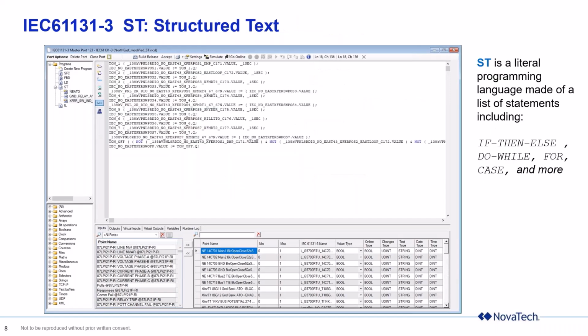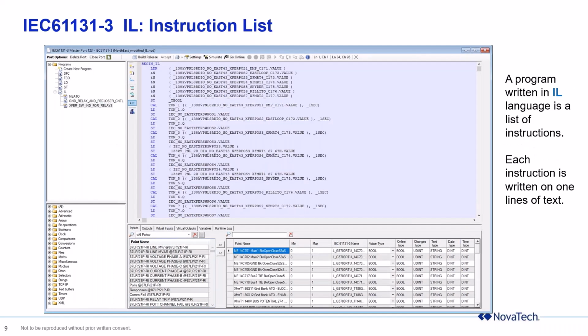And this is an example of what structured text looks like. If you are going to do structured text, I think it's preferred that you do it in Lua or Basic, because that's a lot easier to look at, monitor and see what you're doing. I haven't seen any customer using structured text right now in 61131. Most customers use ladder logic or function block. But if you are using structured text, you do have the if then else, the do while, the for, and so forth.